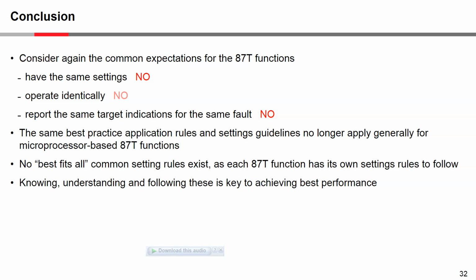compensate. But if you do that, you just have to take the extra precaution that, for some reason, the method used for informing the relay of the tap position could fail. Something could go wrong in that feedback. And so you need to implement means to recognize that has happened. As soon as that happens, the function will realize, hey, I don't know what tap position I'm at anymore. I have a relatively sensitive setting, but because I don't know the tap position anymore, I have to automatically desensitize. So, yeah, hopefully that was the answer you were hoping for.